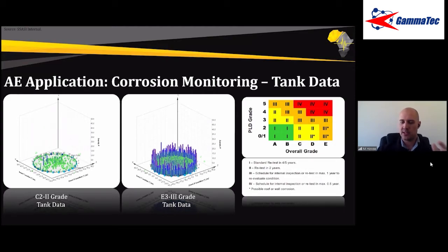Is there a minimal detectable limit? Yes. The limit in our decibel scale, we only go to 100. In general, you have a limit with electronics at about 25-30 decibels. That's all the electronic noise that you can't get rid of. And that's come down from about 30-35 before better boards were made, as it were.